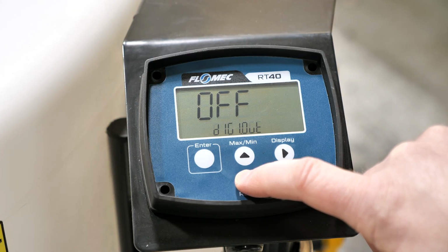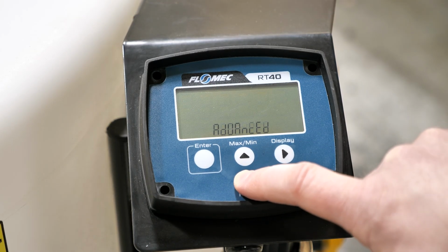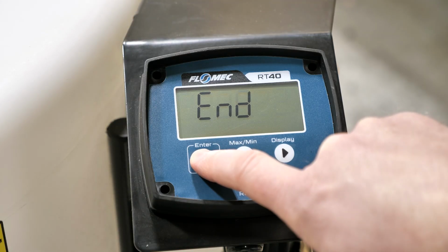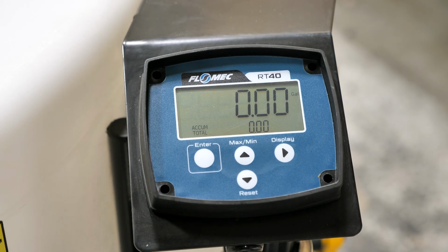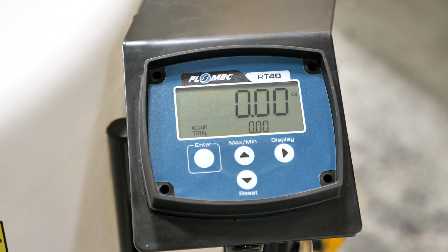Past that, there are no settings that need to be changed. We're going to get through the advanced, the diagnostic, and end. And when you hit the end, you can hit enter, and you will go out of the programming part of the display, and your meter is now calibrated correctly. As with all things, you want to make sure that you test your flow meter before you're using chemicals. So test it with water and make sure everything is functioning correctly before you start using chemical. But that is the setup for the RT40 Flomec meter paired with the F&S direct eduction system.